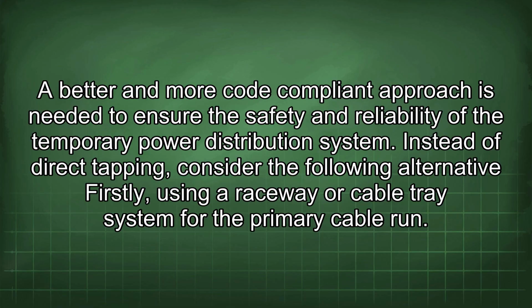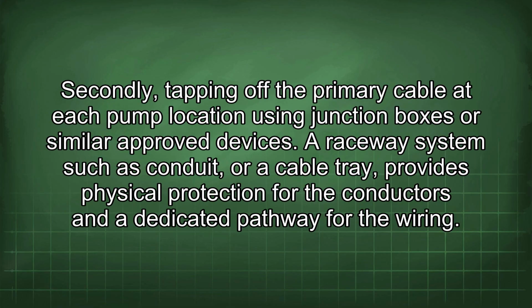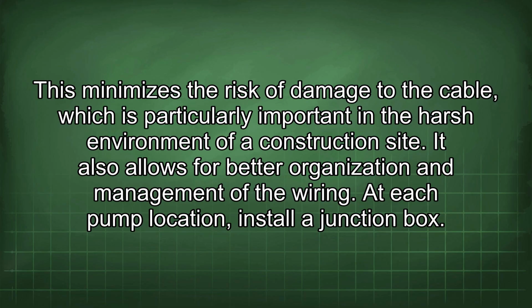Instead of direct tapping, consider the following alternative. Firstly, using a raceway or cable tray system for the primary cable run. Secondly, tapping off the primary cable at each pump location using junction boxes or similar approved devices. A raceway system such as conduit or a cable tray provides physical protection for the conductors and a dedicated pathway for the wiring. This minimizes the risk of damage to the cable, which is particularly important in the harsh environment of a construction site. It also allows for better organization and management of the wiring.